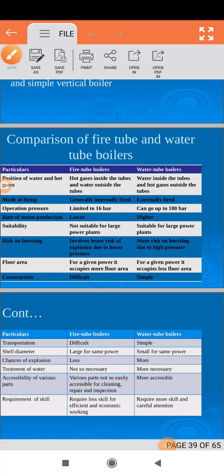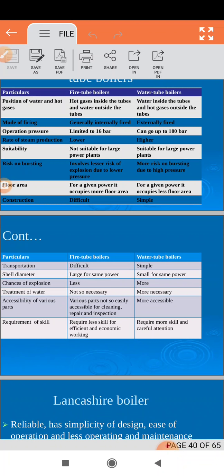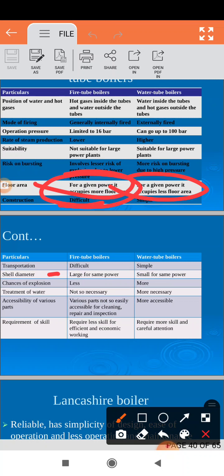Next, construction. Construction is difficult for fire tube boilers; water tube boilers are simpler in construction. Next, transportation. Transportation is difficult for fire tube boilers. Regarding shell diameter: since fire tube boilers require more mass of steam for the same power output, they need a larger shell, so the shell diameter is larger for fire tube boilers. Water tube boilers have a smaller shell diameter for the same output.